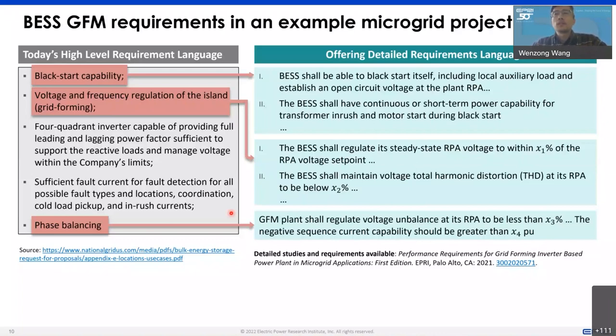For example, if we take phase balancing, then the grid forming inverter should be able to regulate its voltage imbalance at its RPA, which is the reference point of applicability, commonly at the PCC, to be less than a certain percentage. At the same time, you also need to require the negative sequence current capability to be greater than a certain percentage. Of course, these specific numerical values will need to come from studies of specific microgrids, but the way to set up the requirements is what we are investigating.